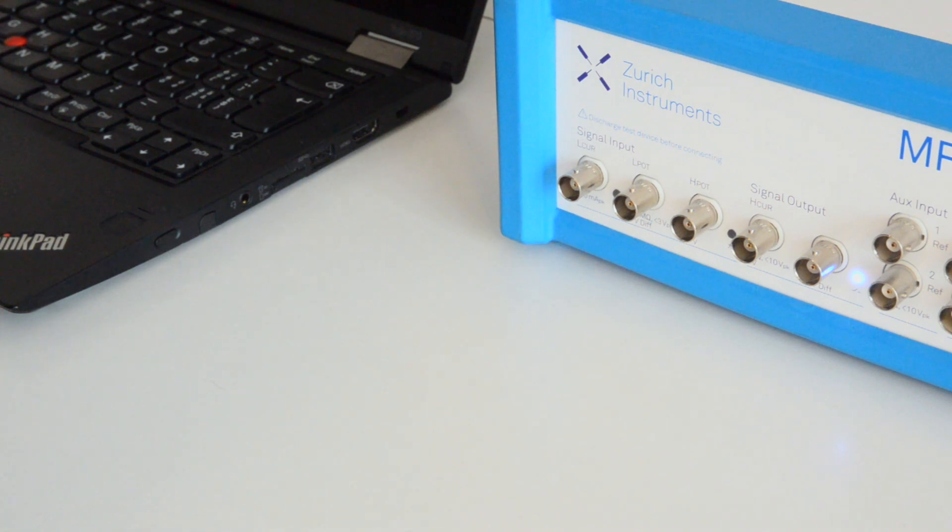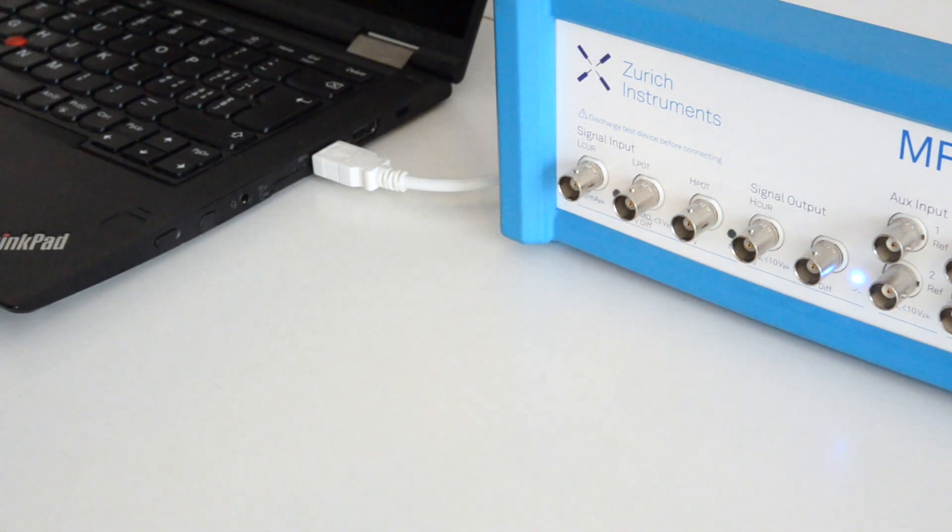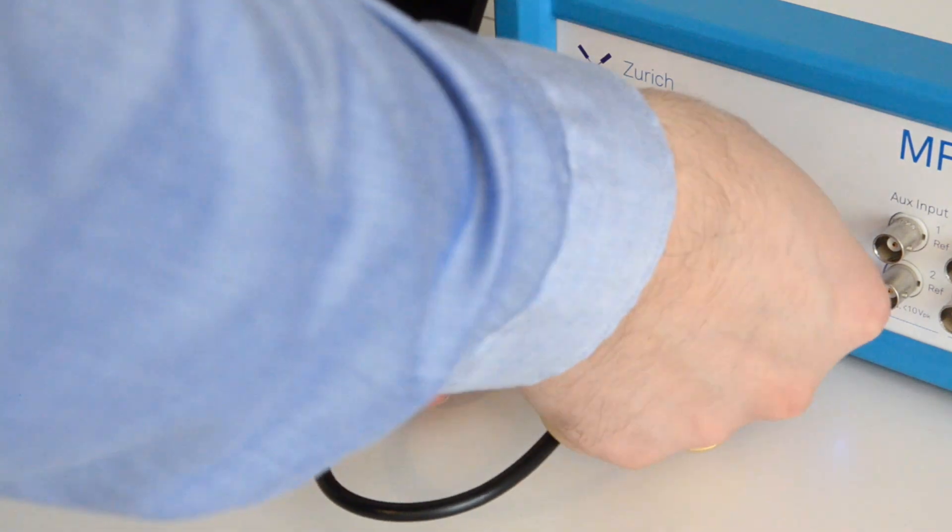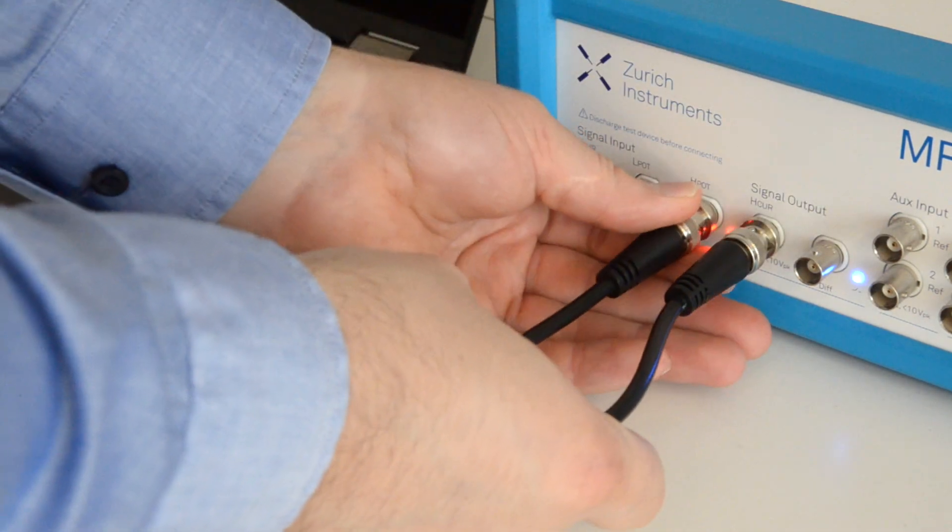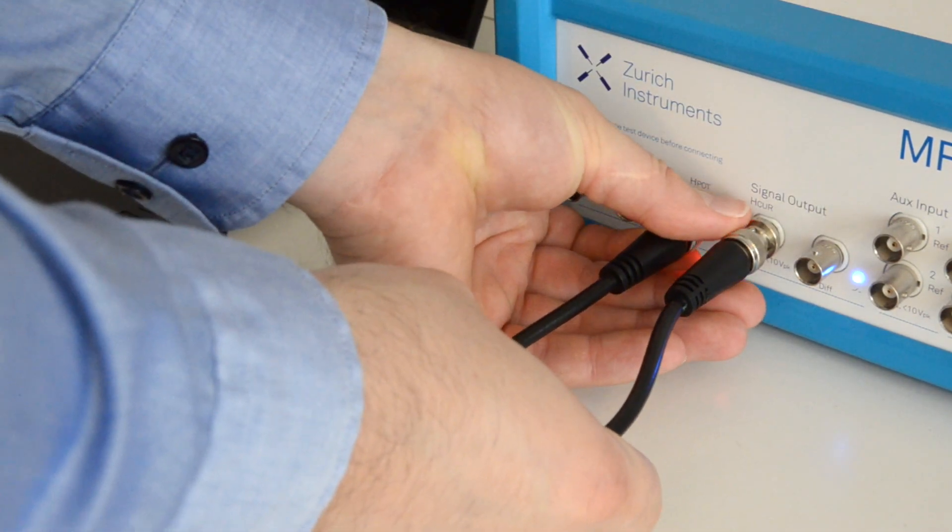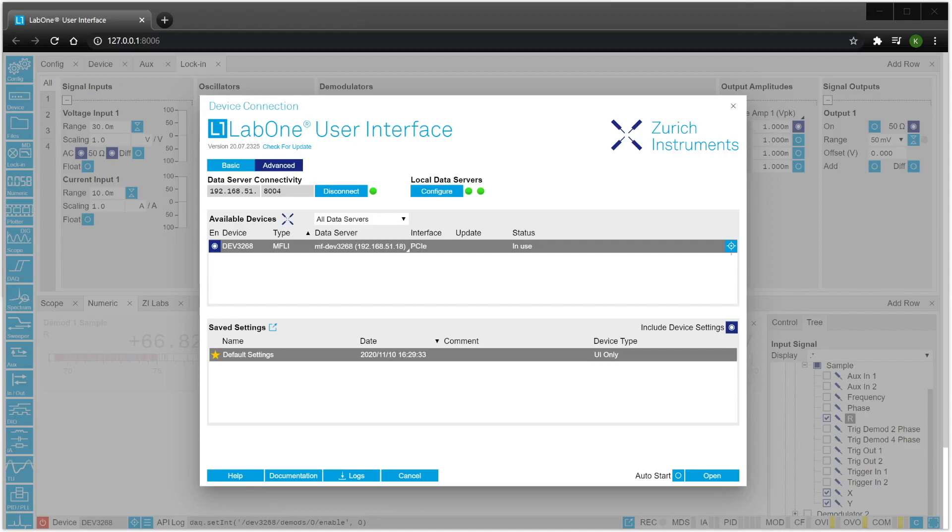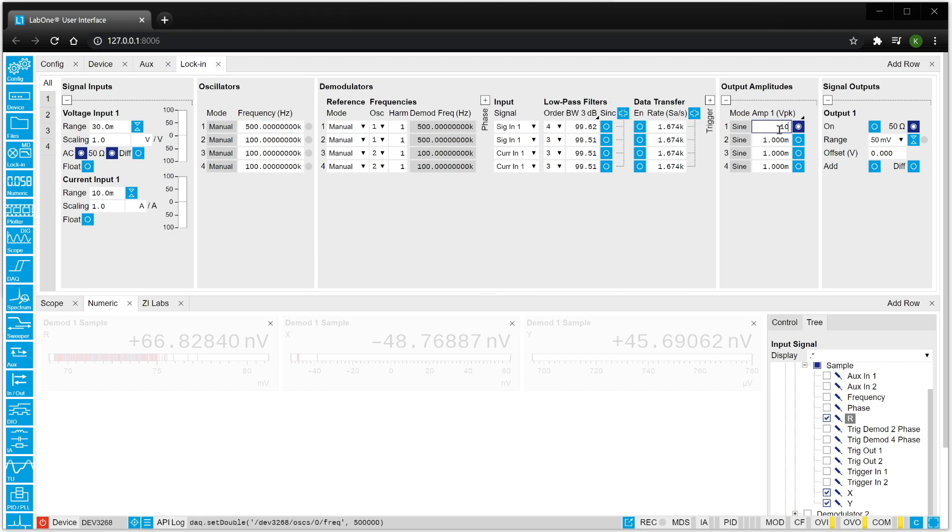First we connect the lock-in to the computer and loop the signal output to the voltage input. Then we launch the LabOne user interface and choose our lock-in amplifier. The UI opens and we define a test signal with a frequency of 500 kHz and 10 mV amplitude. We send this to the output.